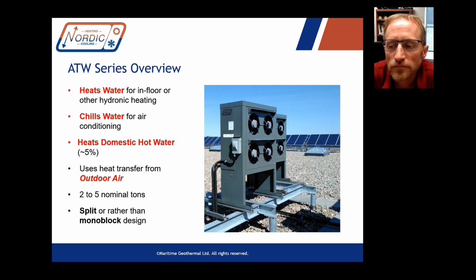So I'm just trying to understand, it's a byproduct. I don't know if that's the right word, but when it's in heating or cooling mode, the desuperheater is basically collecting energy into a separate tank, your domestic water tank, yeah. Water. So that's separate from the buffer tank. The buffer tank contains the closed loop, like in-floor heating water. And then this desuperheater is connected to a totally different circuit, which only has potable water in it. The preheat tank is usually just a 40-gallon. There doesn't have to be anything special about it. The elements aren't even hooked up, but the least expensive kind of tank to get is just, it used to be a $400 tank from Home Depot.